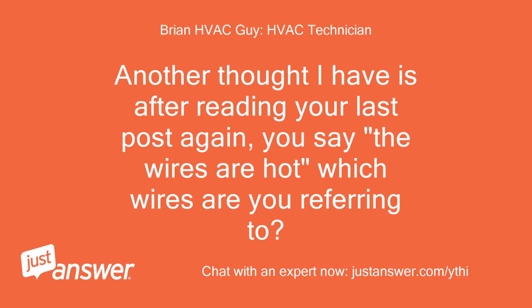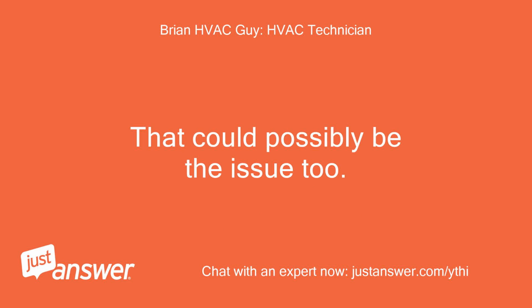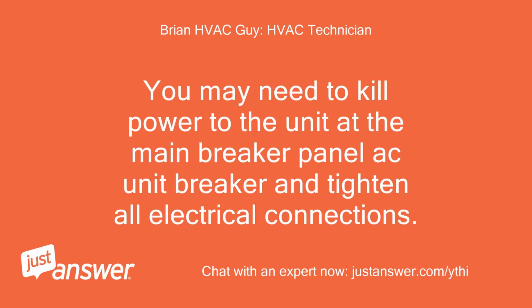Another thought I have is after reading your last post again, you say the wires are hot. Which wires are you referring to? If you have a loose high voltage connection causing low voltage, your compressor and fan motor can cut out on their thermal overload protectors as a result. That could possibly be the issue too. The wire should not really get hot if it's just a dirty condenser coil. You may need to kill power to the unit at the main breaker panel AC unit breaker and tighten all electrical connections.